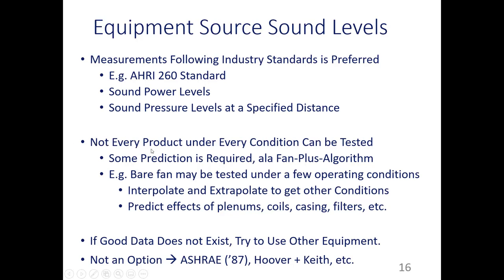But moving on to the next point. It says not every product under every condition can be tested. I touched on this too, so some prediction is required. That's called a Fan-Plus-Algorithm. They measure it at a few operating conditions, and then they interpolate and extrapolate to get other conditions. So, different pressure drops, different capacity of the air that's being delivered, stuff like that. And then there are other things that could be added too, like they might have a lined plenum. They might have an insulated metal casing. Those things might attenuate the noise. Some incorporate silencers into them. Maybe adding in the heat exchange coil might make a difference too. So you need to make adjustments to those few operating conditions that were measured to account for all of the other stuff in these two bullet points.